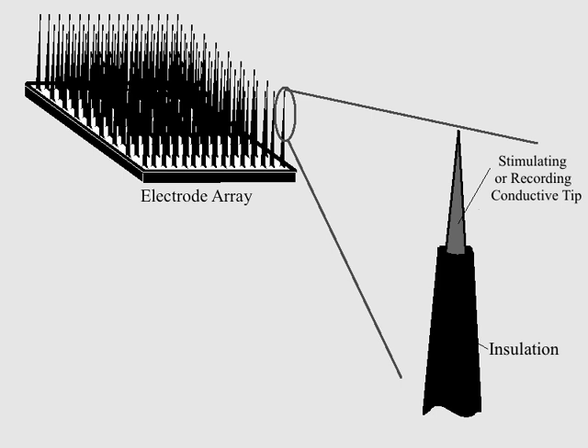Two more conductive materials with notable characteristics are tungsten and indium tin oxide. Tungsten is electrically conductive and can be manufactured down to a very fine point, and for this reason has been used in intraspinal microstimulation for mapping out spinal cords during terminal surgeries. Tungsten electrodes, however, can corrode and form tungstic ions in the presence of H₂O₂ and/or O₂. Tungstic acid has been seen to be highly toxic to cat motor neurons, and for this reason does not currently make a suitable material for chronic implants.